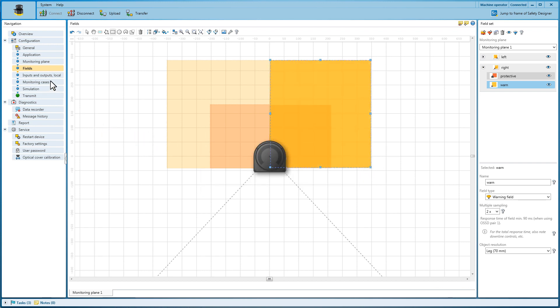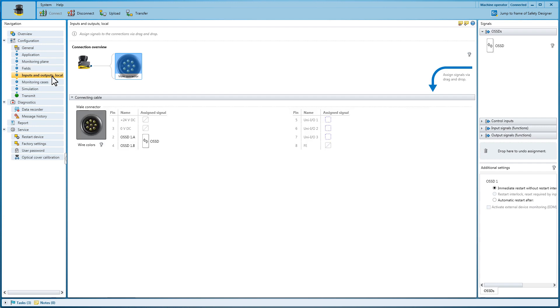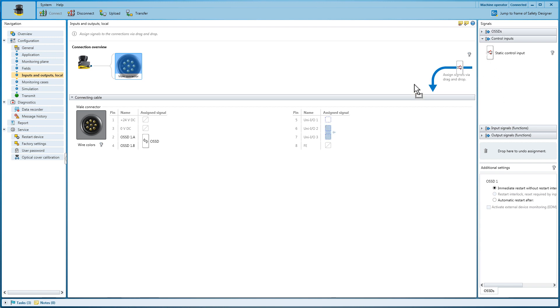The available signal pins are assigned under the Inputs and Outputs item. Three freely assignable pins are available with the Microscan 3 Core I.O. The pins can be assigned both with inputs and outputs. You need a static control input to be able to safely switch between two field sets — just drag and drop.